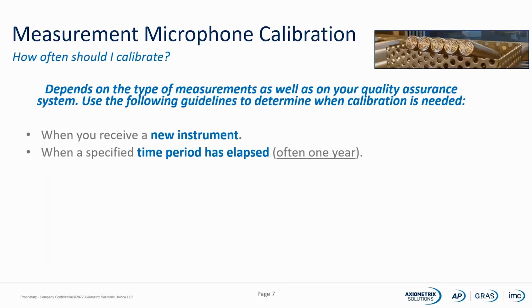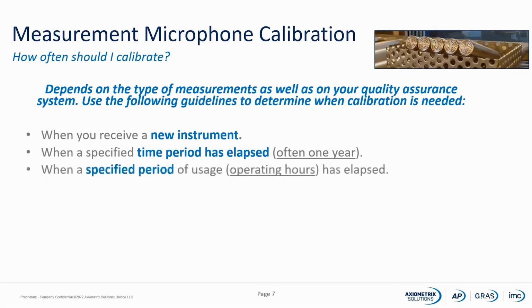When a specific period of time has elapsed, we often recommend that you do a calibration once a year for a microphone. When a specific period of uses or operation hours has elapsed, it could be in your quality system that you say after 1,000 working hours, then we need a calibration of the device.